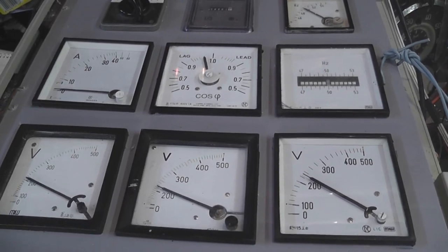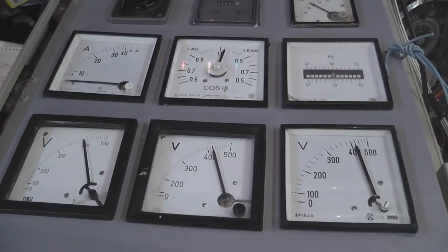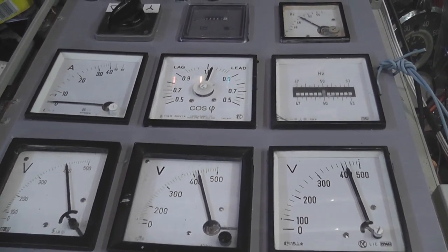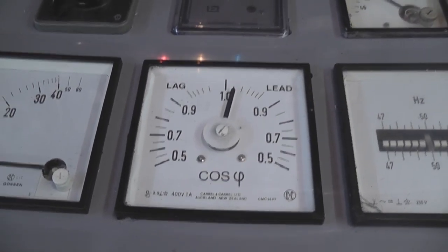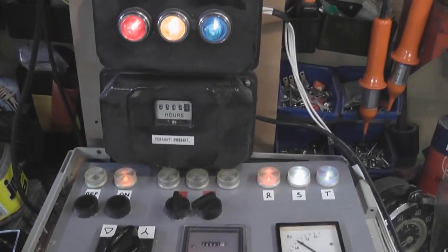I've got it activated — we're sitting at about 220 to 240 volts, and we switch it over to delta, going straight to 400V and it works well. Power factor is even leading — capacitive — sitting at the motor.